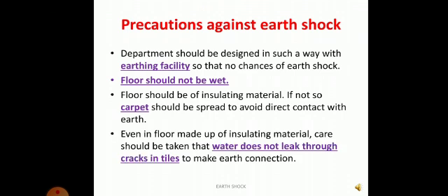Even when the floor is made of insulating material, we must ensure water is not leaking through cracks in the tiles. In public places, flooring is often damaged due to heavy use, and the same can be seen in hospitals that are not well maintained, where floors and tiles are broken. Through these cracks we indirectly make contact with earth, so we must ensure water is not leaking through them.